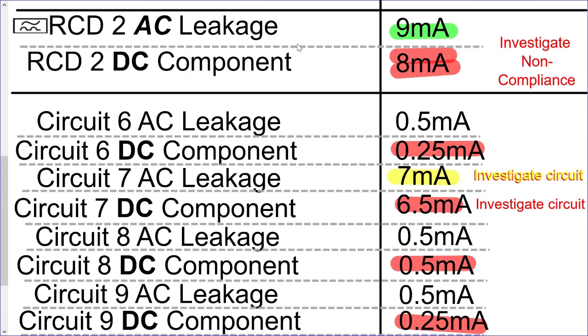Remember, these RCDs are rated at 30 milliamps. They will be providing additional protection, so they should trip within 300 milliseconds if it's a BS EN 61009 RCBO or a BS EN 61008 RCD. So it should trip within 300 milliseconds when it's tested at 1 times its trip rating. Okay, so again, remember folks, it's just a case of just unplugging items of equipment and identifying which items of equipment are actually giving you the higher readings. It's pushing these values up.